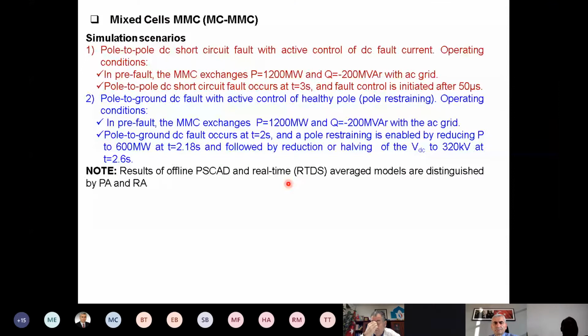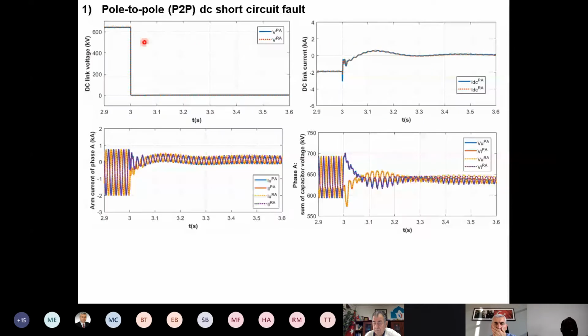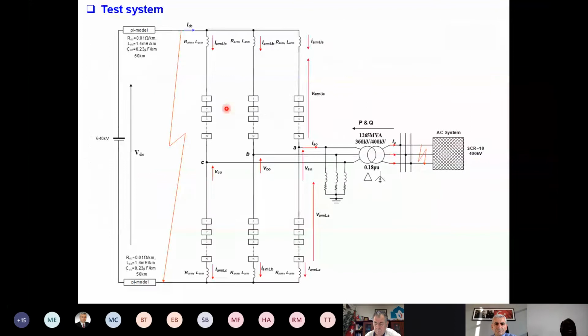And we can see from here, in the first case, we have a pole-to-pole DC short circuit fault, and the other one is a pole-to-ground fault. In the pole-to-pole DC fault, we can see the DC voltage drop from 640 to 0. But in this case, we enable the fault control of the mixed cell MMC. What does the mixed cell MMC mean? We have the half bridge, but here 50% of the cells are full bridge and the other 50% are half bridge, and this is repeated throughout. So 50% of the converter cells are half bridge, and the other 50% are full bridge.